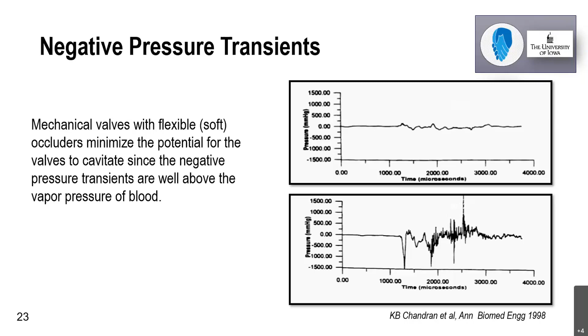And we did a series of studies at the University of Iowa on this, and we found that in the one on the top, which depicts the soft disk valve, the negative pressure formation is extremely low. Because of this, the propensity for formation of cavitation bubbles is very less. While in the case of hard disk material, negative pressures of the tune of minus 1500 millimeter of mercury can instantaneously form at the distal or the outflow side of the device. Of course, this negative pressure lasts for a few microseconds only, but that is good enough to generate the vapor bubbles and collapse of these bubbles.